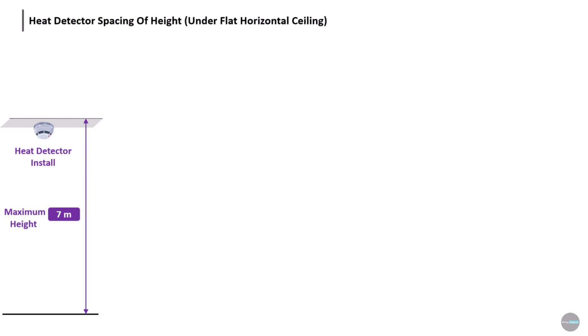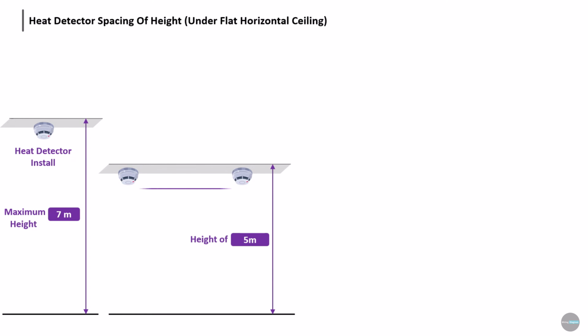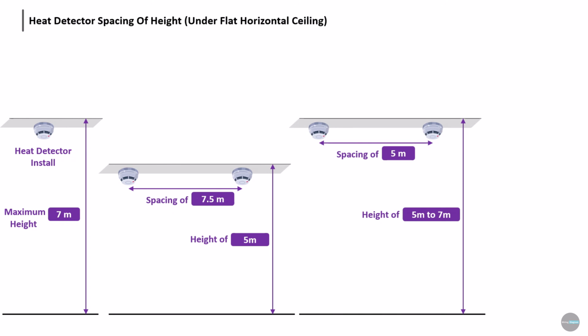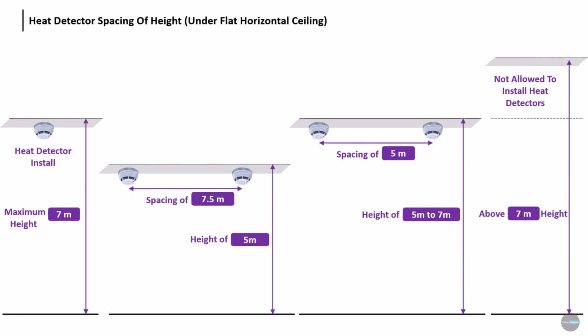Heat detector spacing with ceiling height. According to standard, a heat detector can be mounted up to 7 meters in height. If the ceiling height is up to 5 meters, then the spacing between detectors should be 7.5 meters. If the ceiling height is between 5 and 7 meters, then the spacing should be 5 meters.